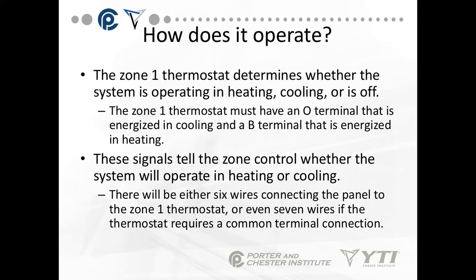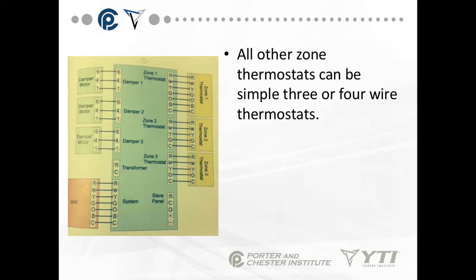There are either six wires connected to the panel by the Zone 1 thermostat, or seven wires if the thermostat requires a common terminal connection. Think about that when you're doing your wire sizing for a new installation. All other zone control thermostats can be simple three- or four-wire thermostats. Zone 2 and Zone 3 can be the simple thermostats, and can have a C terminal for digital thermostats that require a common.